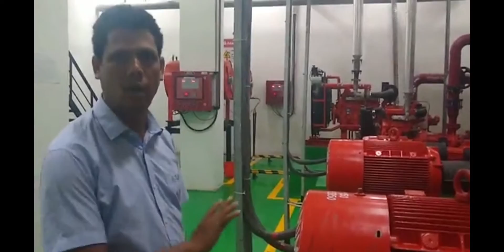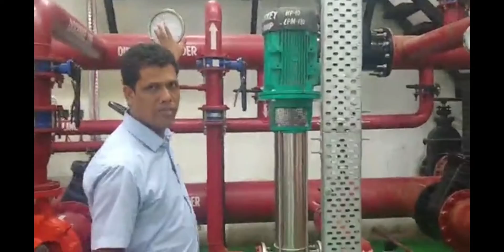There is a jockey pump; we have already mentioned the pressure. This is a system that is automatically on and automatically off. The pressure cut-off is 10 kg and cut-on is 8 kg as per design. Exactly, we have the design sheet over here. Then we come to the hydrant pump.